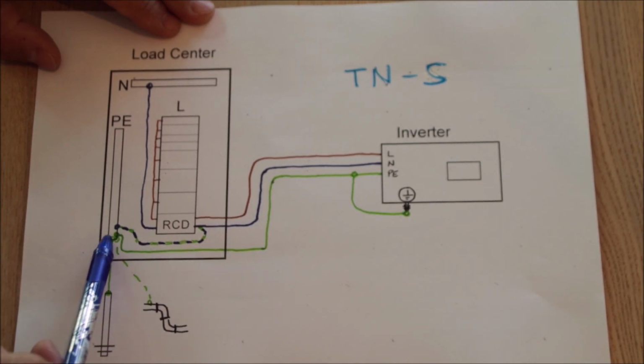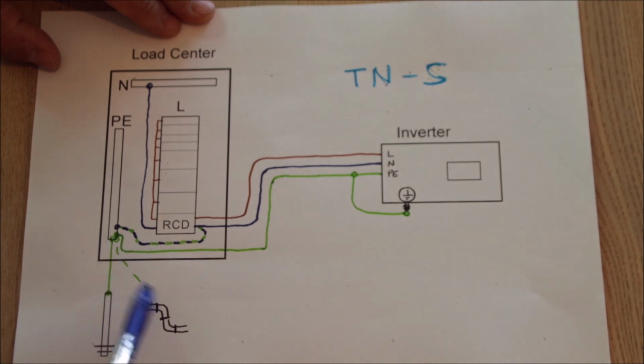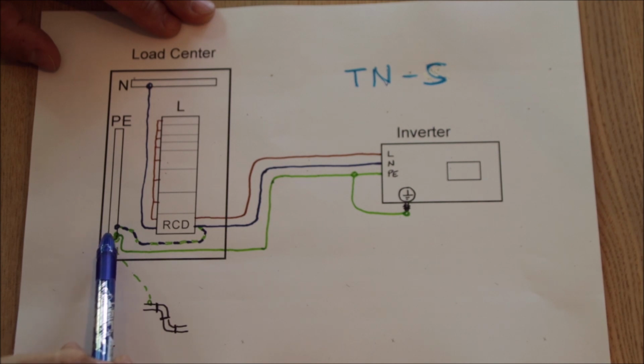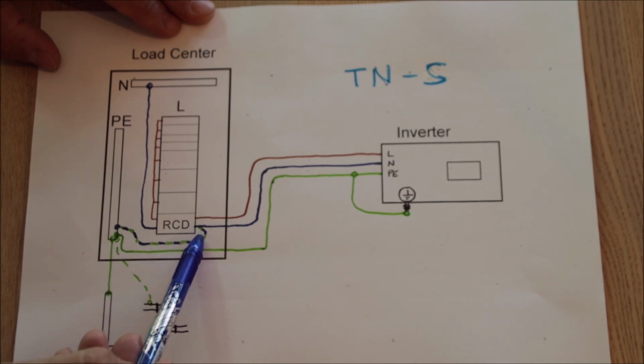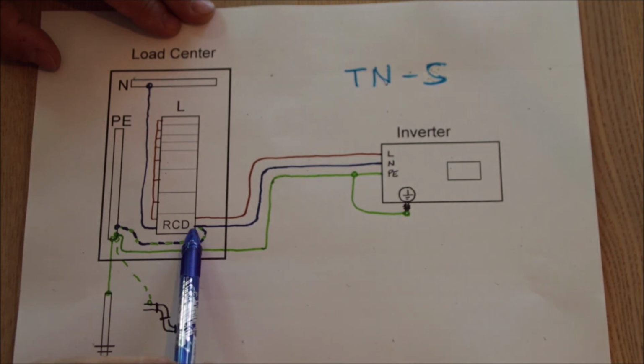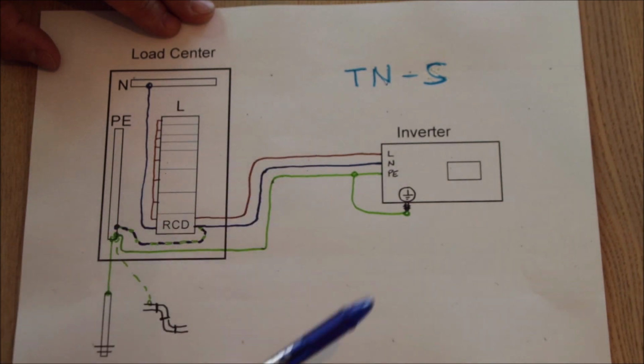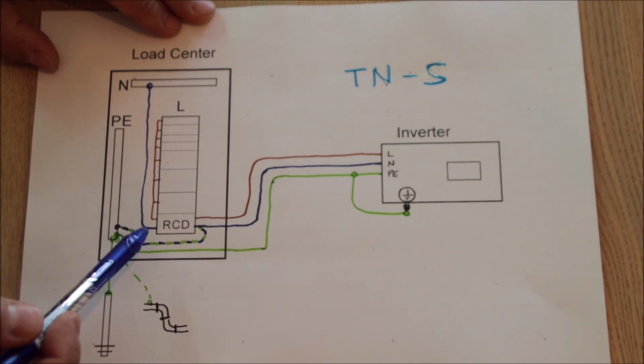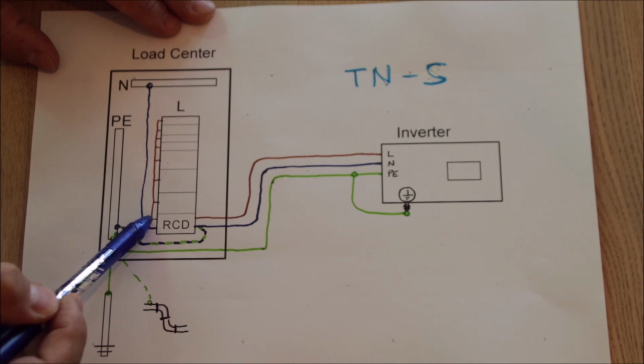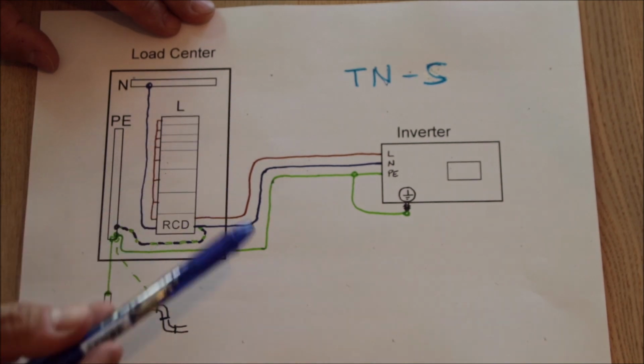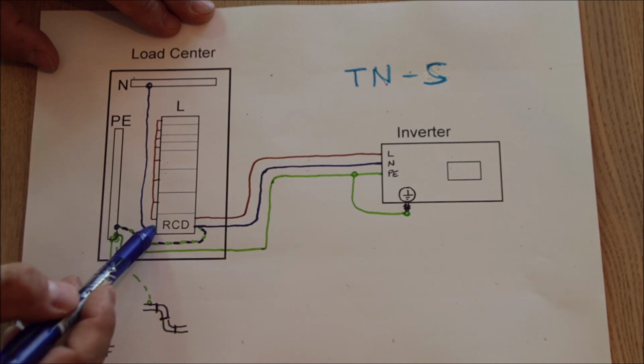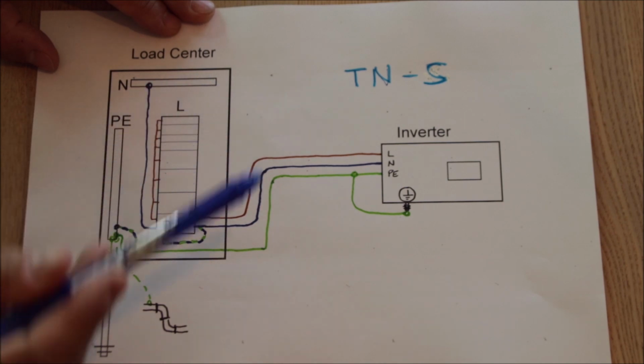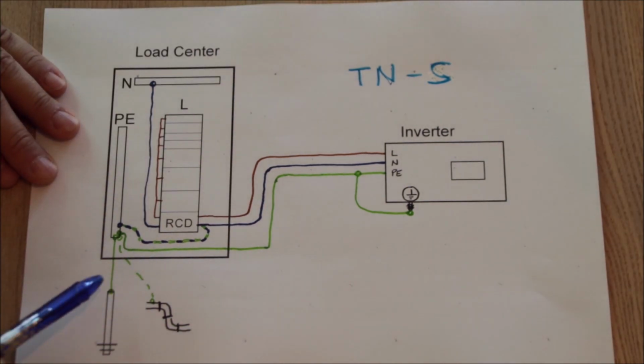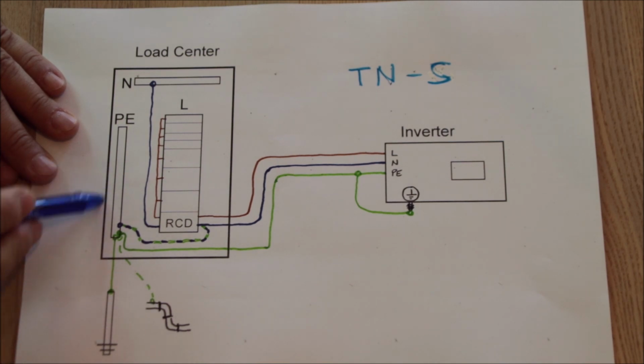After that, here inside the load center, there's one thing missing. We need to bond now. So we take a jumper from the PE bar and go to the input side N to the RCD. This is now our bonding, and we have turned the IT system into a TN system. Yeah, and the outputs of the RCD, as everywhere else in every different system, L goes then to the individual circuit breakers, and you use them to supply your loads, and the output of the neutral goes to the neutral bar, and you take the other neutrals to your loads. If there is anything else to bond to earth, like metal pipes, gas pipes, copper pipes, whatever, you also bond it to your PE bar here.